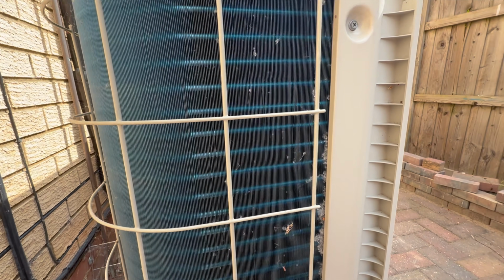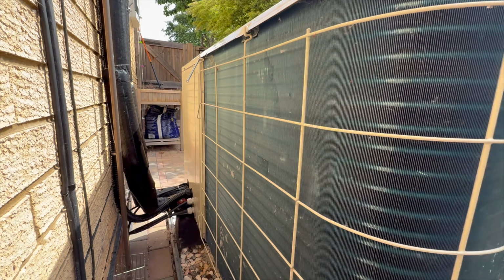So there is one other thing that happens with our heat pump, and this could be specific to where I live. But just behind us over there is a large set of farmers' fields. We get a lot of blossom and just detritus blowing in on the wind, and I've noticed on the back of the heat pump there you can start to see there's bits of fluff building up on it, and it just means I need to occasionally go out there with my shop vac and just kind of hoover it off to make sure none of that fluff ends up jammed between the vanes of the radiator. But again, all really minor things. The heat pump itself has performed flawlessly for the last 6 months.